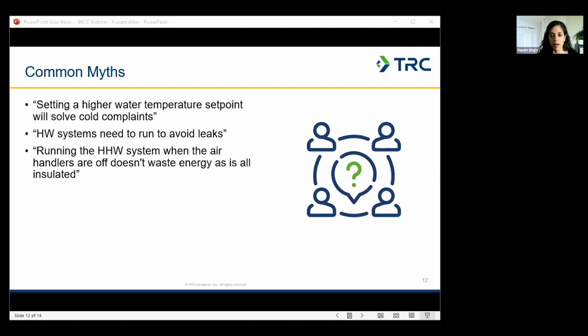Another myth is that you have to run the hot water system 24/7 to avoid leaks. This is a pretty prevalent thought among building operators, and it may be a valid concern in some older buildings, but not all, and it's certainly not an issue for buildings built within the last 20 years. This myth persists because maybe an operator had an issue once with leaking valves, so they conservatively operate the building ever after to avoid that issue, and may even pass that myth along to operators who come after them.